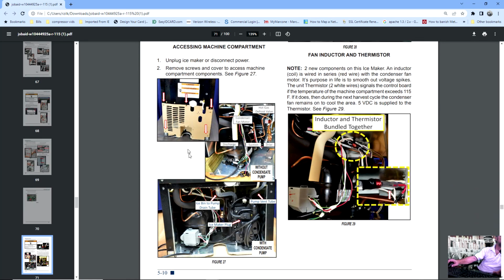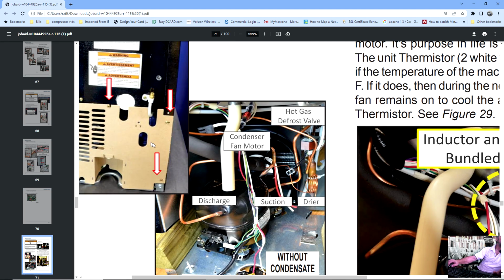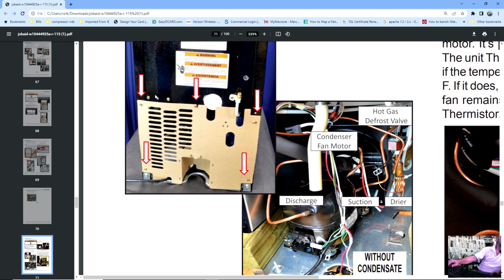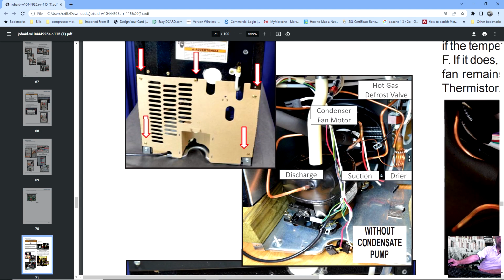Okay, here's that picture. On the back of this unit, you can see two screws, and it's hard to tell, but there's a panel here that's bent. This panel is hiding the water fill tube and your refrigerant lines that are running from your compressor to your evaporator. If you had to change your evaporator, you have to remove this rear cover so you can get to those lines. So here's our dryer filter and our cap tube, suction line, regular components, condenser, fan.